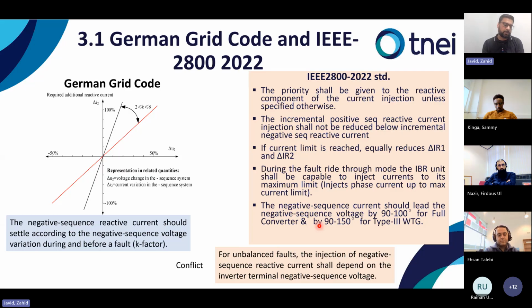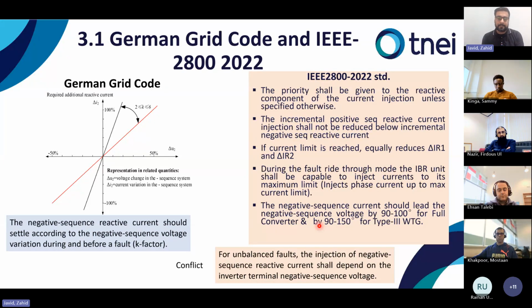And there is also one clause that says that for unbalanced faults, the injection of the negative sequence current shall depend on the inverter terminal negative-sequence voltage, which is in conflict with the German grid code. So while we are defining the current limiting strategy, we should be very careful about that. And when we are developing those IBR models, we should generalize them so that they can be adopted for a grid code that is competing with this standard. And how can we generalize it so it can work for both, by adopting very minor modifications to those sequence domain models?